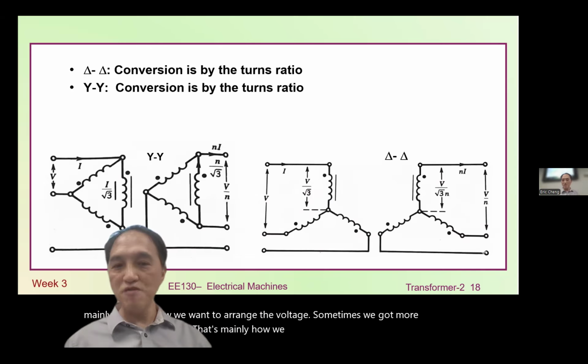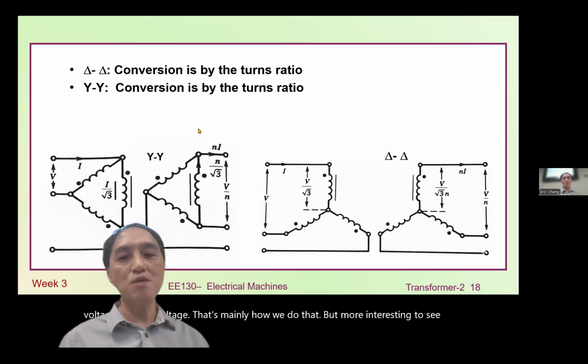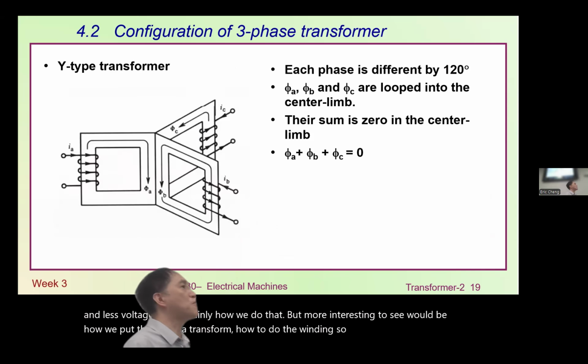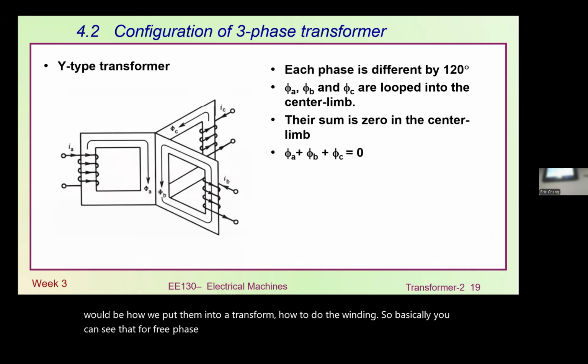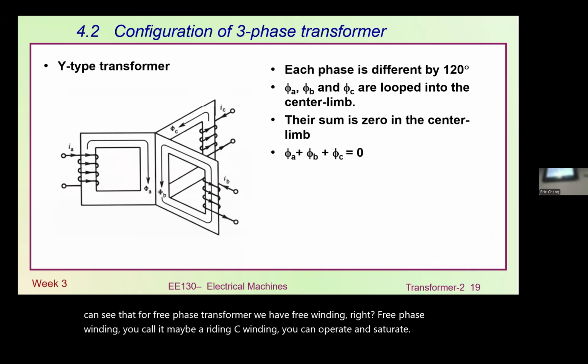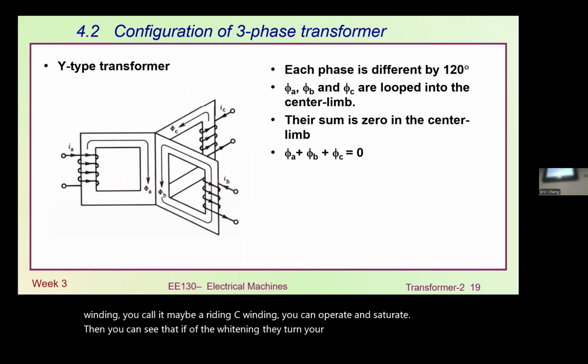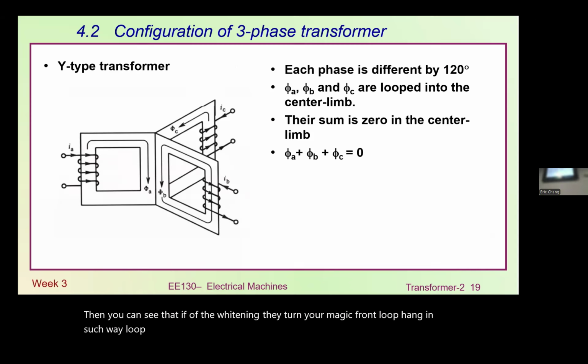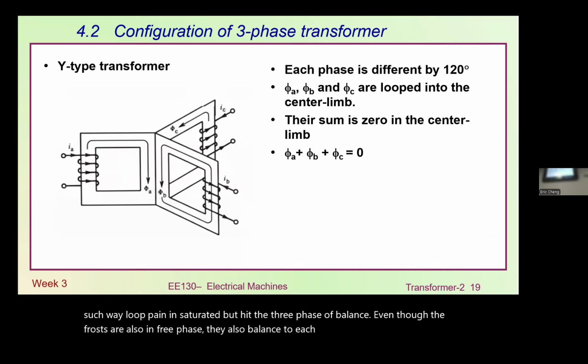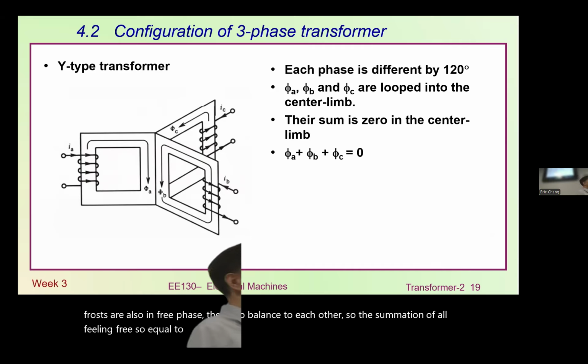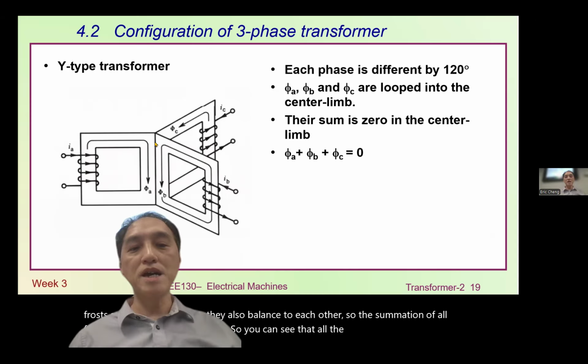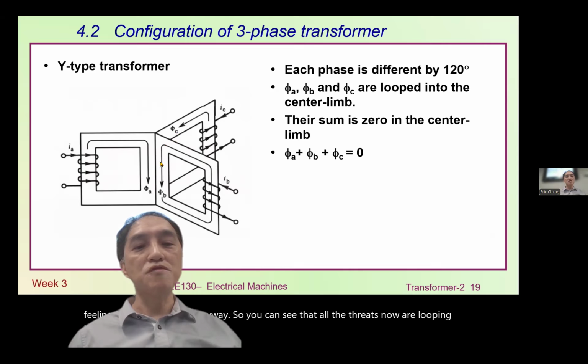But more interesting will be how we put them into a transformer, how to do the winding. Basically, for a three-phase transformer, we have three windings, right? Three-phase winding, you call it maybe A winding, B winding, C winding. You can arrange them in such a way, then you can see that each winding generates magnetic flux looping in such a way. But if the three phases are balanced, even though the flux is also in three phases, they also balance each other, so the summation of all three phases should equal 0 anyway. So you can see that all the flux now loop into the center here, then the summation of flux equals 0.